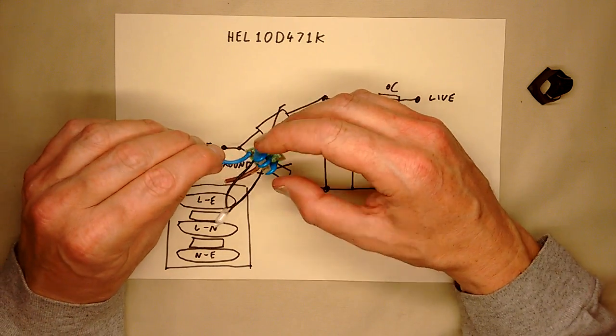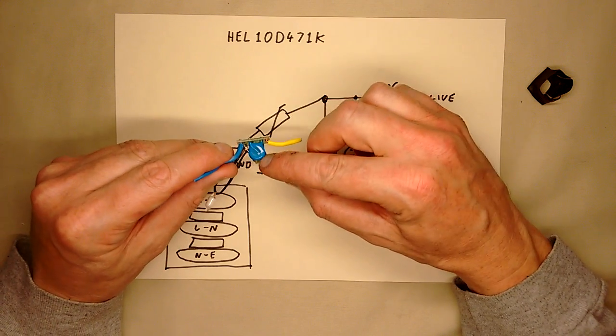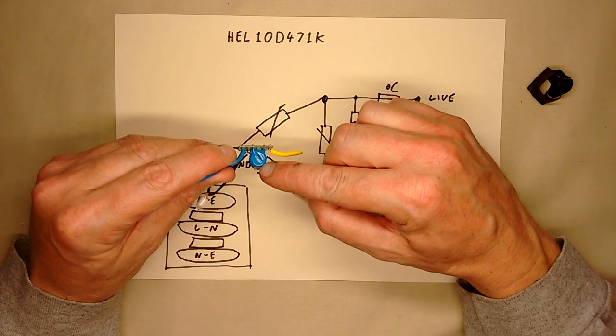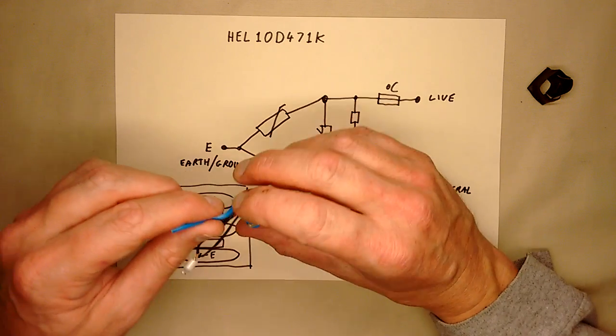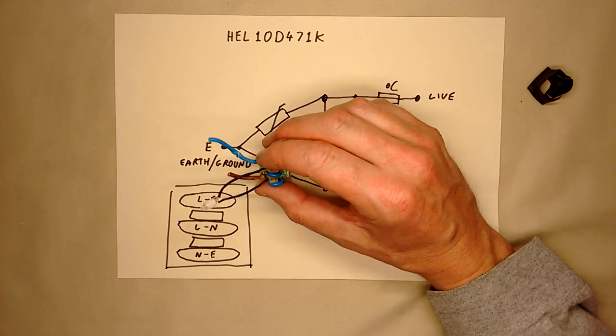But the nature of these metal oxide varistors is that every time they absorb a transient, every time their voltage is exceeded, they just end up failing a little bit internally.